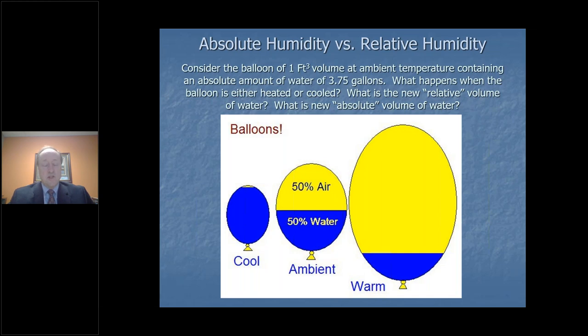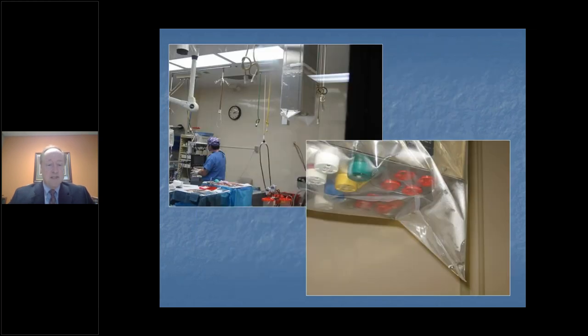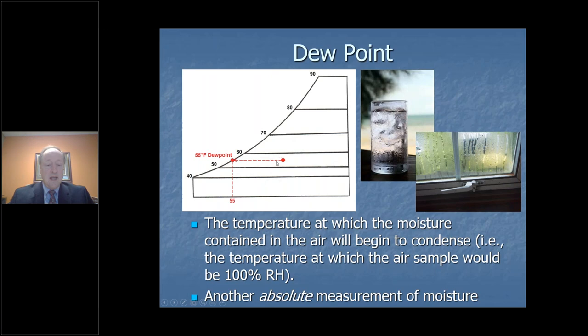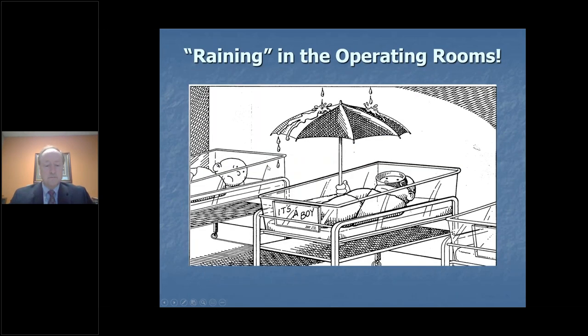So when you go to the psychrometric chart and you measure the dew point temperature, we're back up a slide or two. See, if I'm at the same moisture level, if I'm here at 75 degrees Fahrenheit, but I reduce that to 55 degrees Fahrenheit and I did not remove any moisture from the air, I'm still at a 55 degree dew point. What's my relative humidity here? It would be 100%. You know, 80% here, 70%, et cetera. So hopefully that helps you understand the differences between absolute and relative humidity.